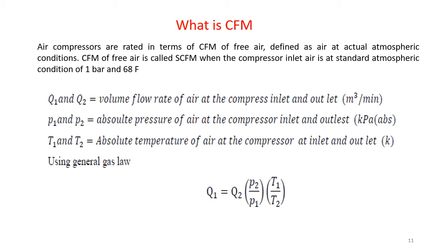So what is CFM? Air compressors are rated in terms of CFM, or CFM of free air, defined as air at actual atmospheric conditions. So CFM for free air is called SCFM when the compressor inlet air is at standard atmospheric condition, that is 1 bar and 68 degrees Fahrenheit. So CFM and free air delivery are some important terminologies related to compressors which you already studied.